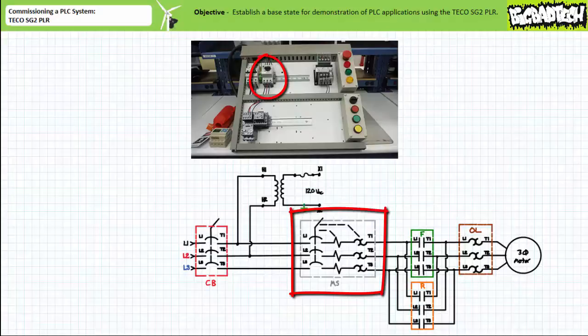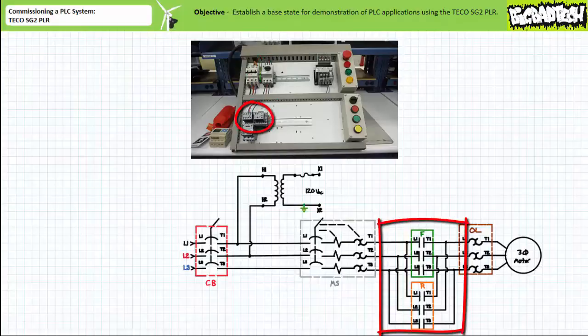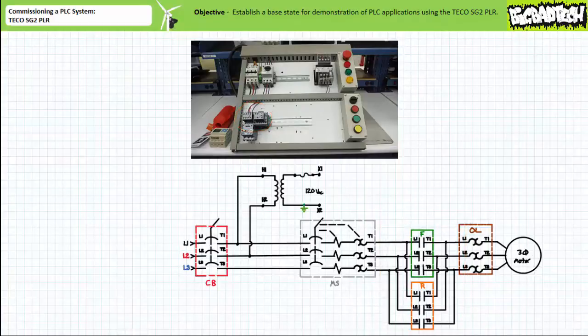Also, downstream of the main circuit breaker is a manual motor starter that makes or breaks connection to paired contactors wired such that the F contactor induces forward rotation and the R contactor induces reverse rotation of the 3-phase AC induction motor. The contactors are mechanically interlocked with one another such that they may not be simultaneously closed. Let's assume the F contactor is on the left and the R contactor is on the right. Additionally, a single overload relay serves to protect the motor from sustained overload conditions. Let's leave the motor unattached for now.